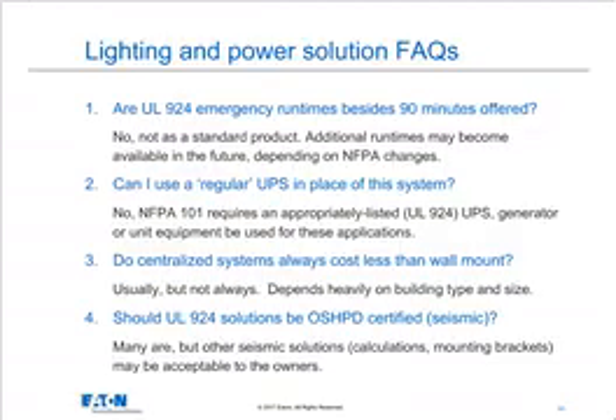Are UL 924 emergency run times besides 90 minutes offered? Other than the UL 924 auxiliary, most UPS and emergency lighting vendors will offer 90 minutes or 2 hours, usually not more than that. The UL guidelines that we have to test to achieve UL 924 compliance are based around 90 minutes. So the answer is really, as a standard product, we're talking about a 90-minute battery backup.